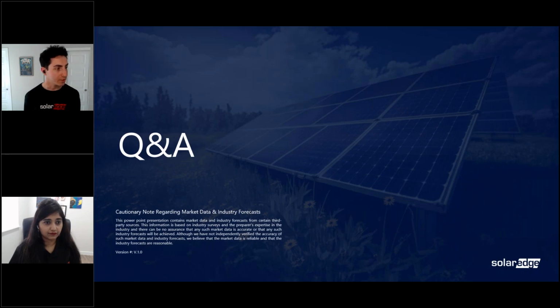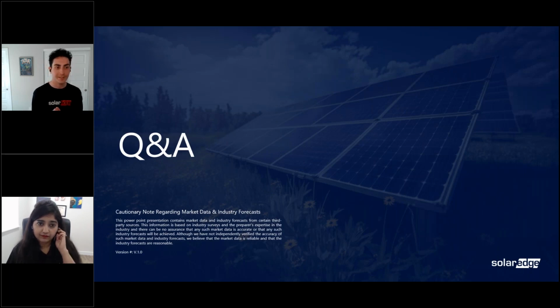So, good question. A UL 3741 offering is a solution for 690.12. So if you go and look at 690.12, one of the options listed under it is 3741. And I think actually, Chris, your next question is getting at the meat here, which is if you've already got an optimizer, why do you need a 3741 listing? And the threshold there is that 80 volt threshold.